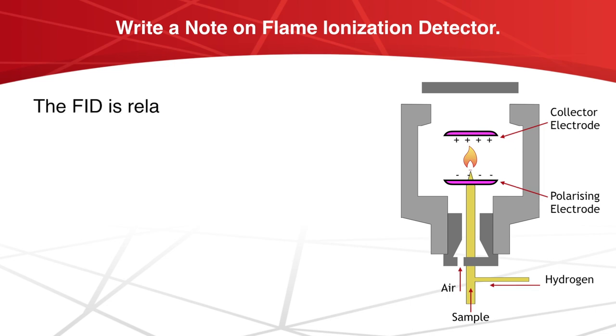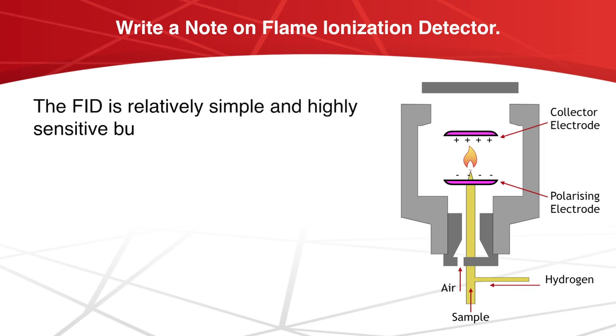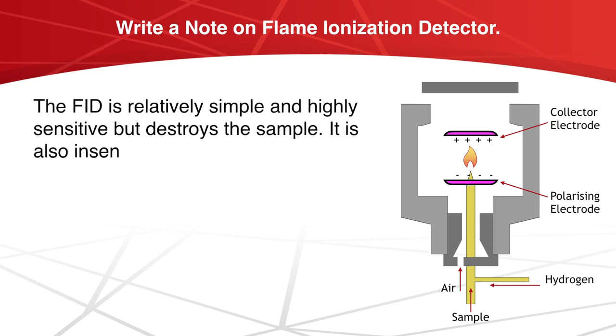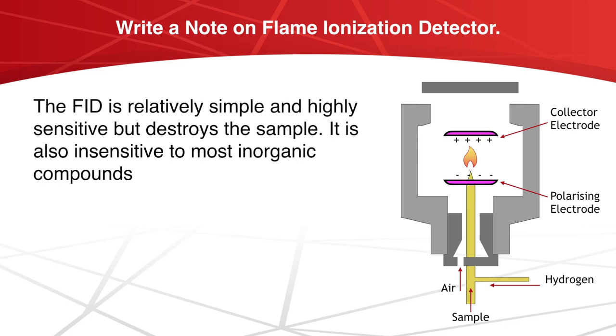The FID is relatively simple and highly sensitive but destroys the sample. It is also insensitive to most inorganic compounds like water vapor and air.